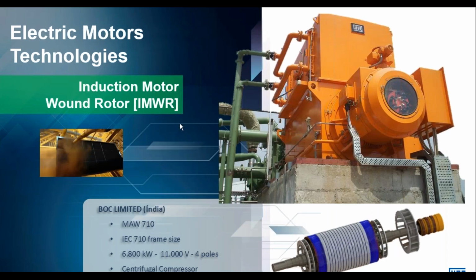Then we look at a wound rotor induction machine. This is also an induction motor. However, we replace the rotor with a wound rotor, and we link it to an external rheostat resistance in order to change the resistance of the rotor during the startup process. This allows us to increase the starting torque. In fact, if the rheostat is dimensioned correctly, the limitation here during startup is only limited by the breakdown torque of the machine.